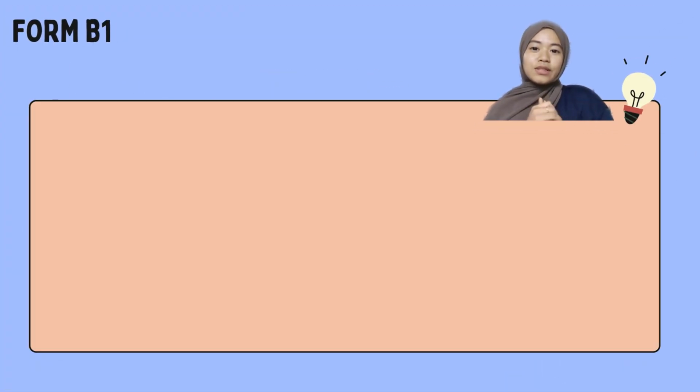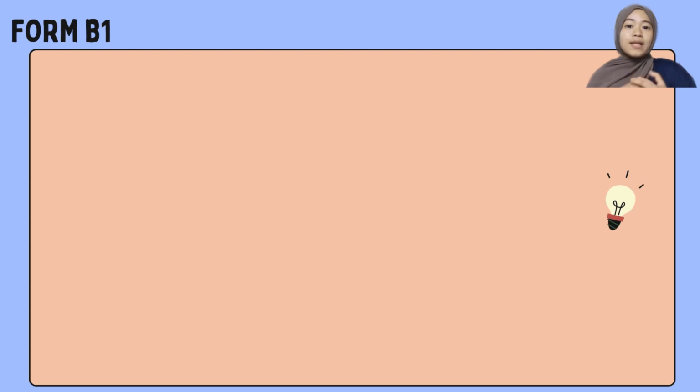Let's break down the most critical hazardous ingredients on our list one by one to show how these parameters determine our final hazard rating, HR, on a scale of 1 to 5. First, methanol. It is handled in a volatile liquid form. Its hazard classification is flammable liquid and acute toxicity. It carries code H225 for high flammability, alongside H301, H311, and H331, meaning it is toxic if swallowed, inhaled, or in contact with skin. This assigns it the maximum hazard rating of 5, HR5.